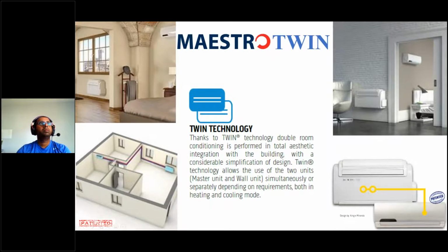So this is the Maestro Twin. This is a self-contained unit, a Maestro, that mounts on an outside wall, and then you run refrigerant lines and an electrical line from the main unit to the fan coil that gets mounted in another room. So now the unit can split its capacity between those two rooms, and you can cover more ground and have a more comfortable space. This will be very similar to a multi-zone mini split, where you run your refrigerant lines, your power goes to the main unit, and then you run communication line and power from that unit to the indoor unit. And we're kind of looking forward to that as our next release.